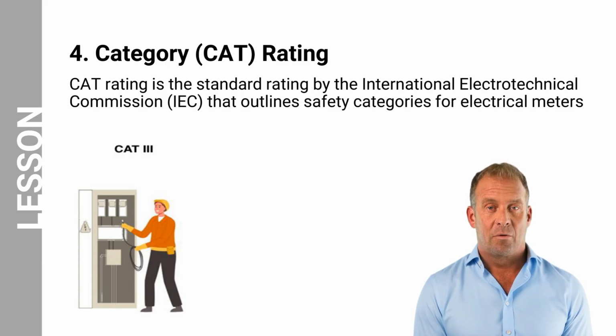CAT stands for category and is a standard rating established by the International Electrotechnical Commission, abbreviated as IEC, to define safety categories for electrical meters and other test equipment. CAT ratings indicate the level of protection the equipment provides against overvoltages that may occur on power distribution systems. They consist of 4 categories: CAT 1, CAT 2, CAT 3, and CAT 4, with CAT 4 being the highest level of protection and CAT 1 being the lowest. These ratings help users select the appropriate test equipment for specific applications and ensure safe operation in various electrical environments.